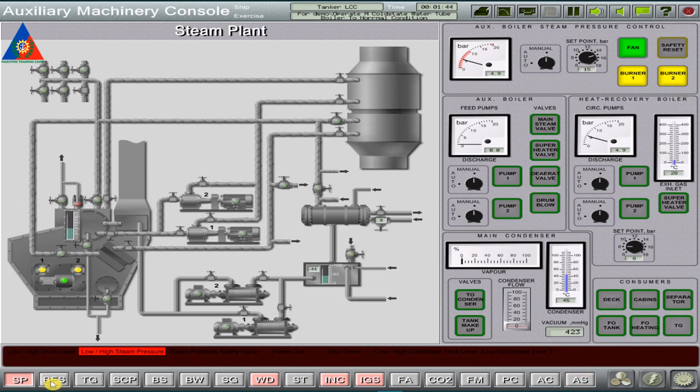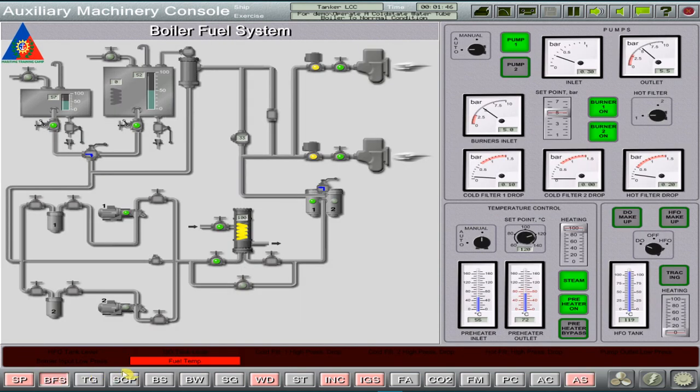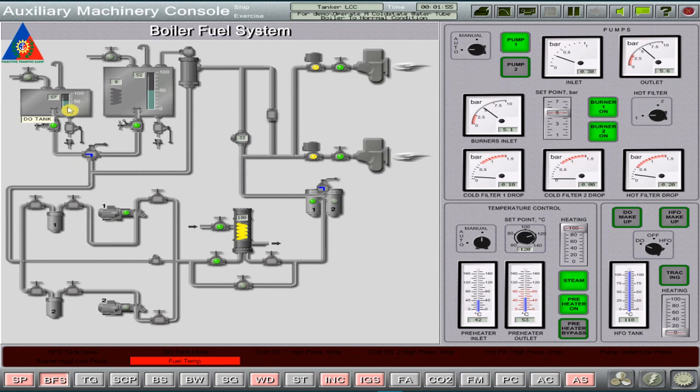If any alarms occur, just acknowledge it. We have a low fuel temp alarm which means no steam is present in the fuel preheater and we have a cold diesel circulating in the system.